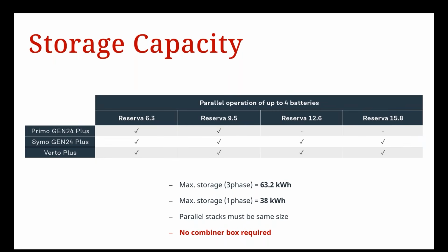Let's have a look at the max storage capacity in every possible setup. On the Primo and single phase inverters, we can do 3 battery modules, giving us 9.5 kilowatt hours. On our Symos, we can go to 15.8 per tower, similar to the Verto Plus. This gives us a max setup in a multi-tower scenario for 3-phase with a whopping 63.2 kilowatt hours, and in a single phase scenario, 38 kilowatt hours. Please note that all parallel stacks must have the same size in terms of battery modules.